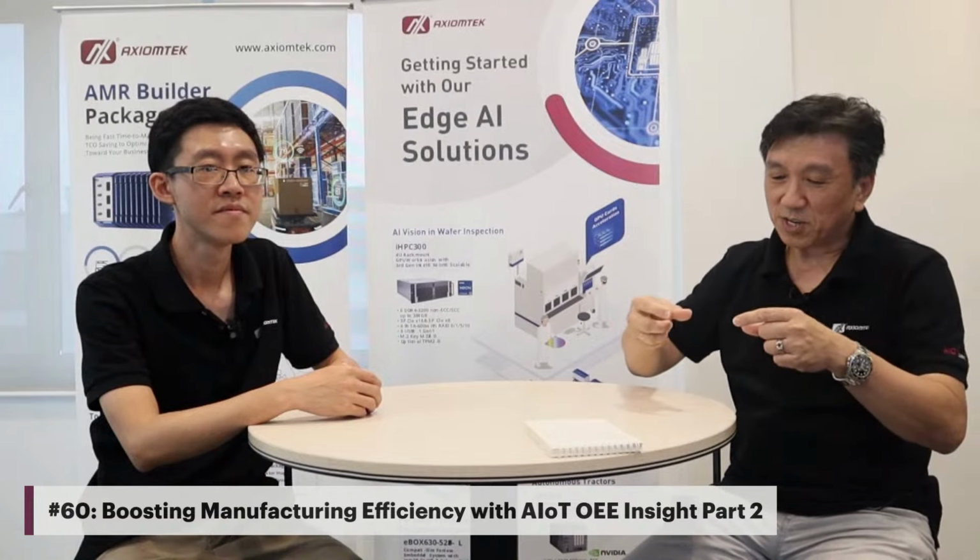There is one part, if you still remember, where we do non-intrusive extraction, not actually computer vision but more of OCR. Especially for the legacy, old machines, they have a VGA cable to drive the monitor, but you don't have anywhere to tap onto any data. So you can intercept with one device that translates the video onto a screen. Then you can use vision AI, or some algorithm, to do the OCR from the screen. So you can also extract data from there.